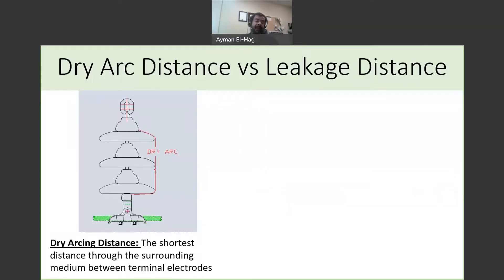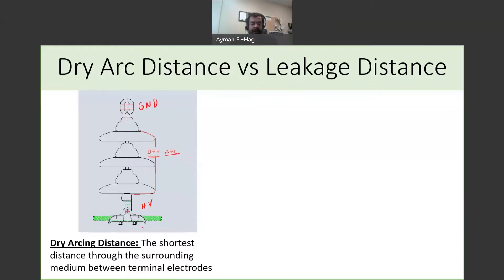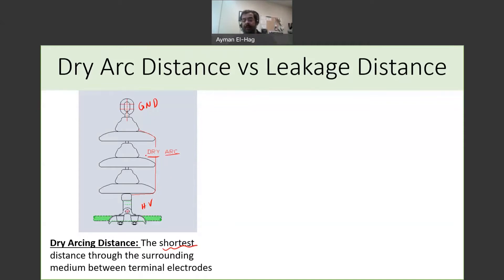The first definition we want to understand is called the dry arc distance. This is a cascaded cap and pin insulator. The dry arc distance is basically the shortest distance through the surrounding medium between terminal electrodes. So if this is your high voltage end and this is your ground end, the dry arc distance is the shortest path through air that bridges the high voltage with the ground end. The dry arc distance is responsible for the dry flashover — a flashover that happens in air and not on the surface.